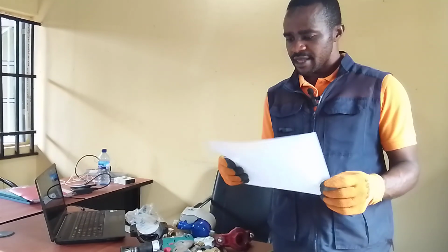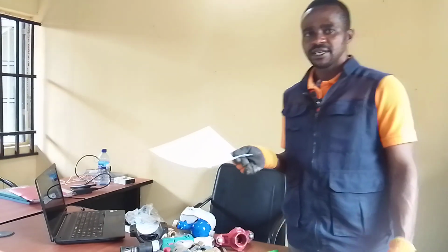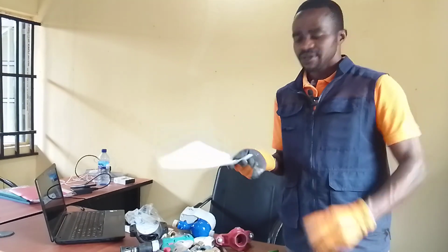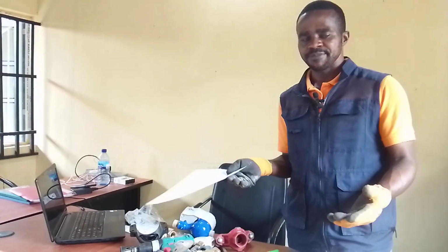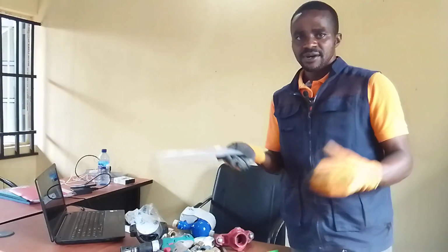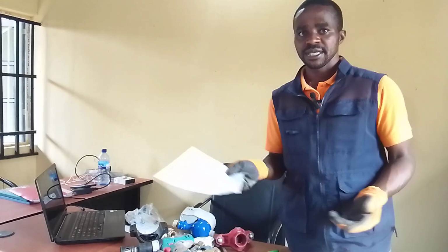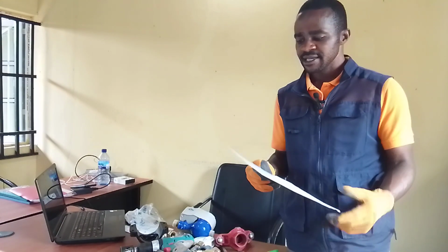So the other time I talked about your cable sizing when you are installing your submersible pump, right? This is very, very important because a lot of pumps, submersible pumps especially, are underperforming or having electrical or even mechanical issues because of undersizing of cables, right?